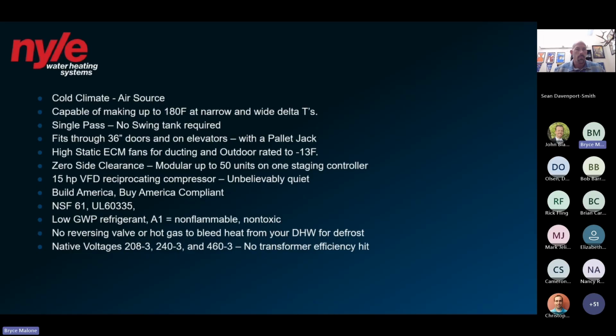Here's where it really starts to differentiate. Many have tried and many have failed to do return to primary single pass systems. You cannot do that unless you are using a variable speed compressor and a variable frequency drive. So those that have tried and sadly have failed use a fixed speed compressor, and that's why they have the issues that they have, because it just can't handle it.